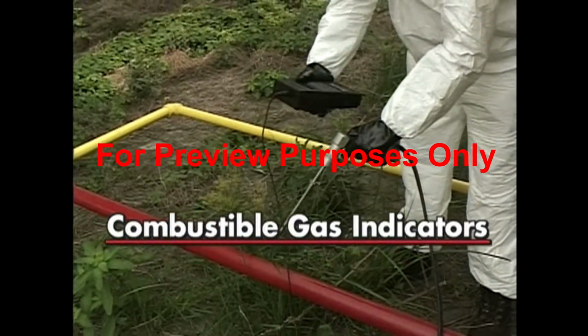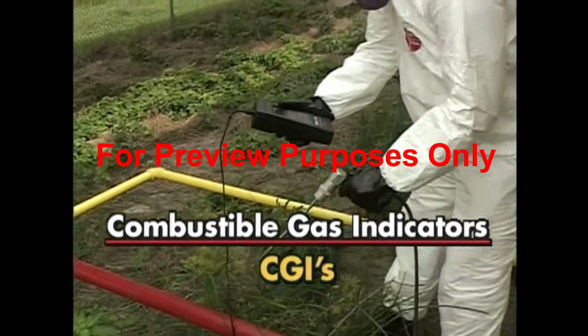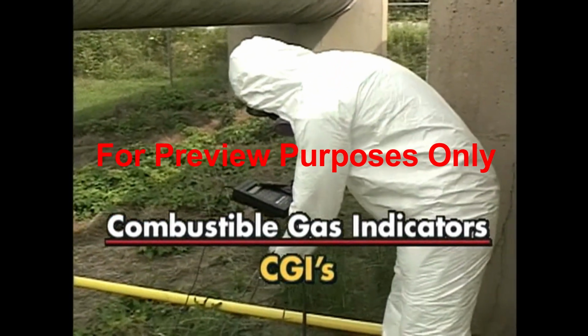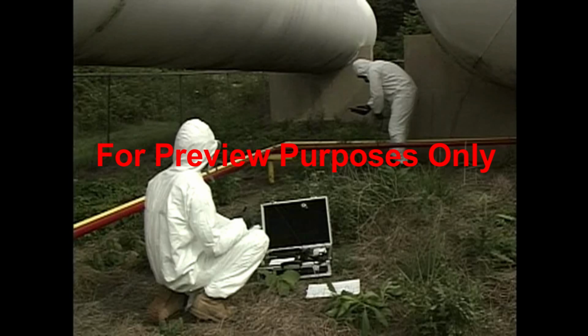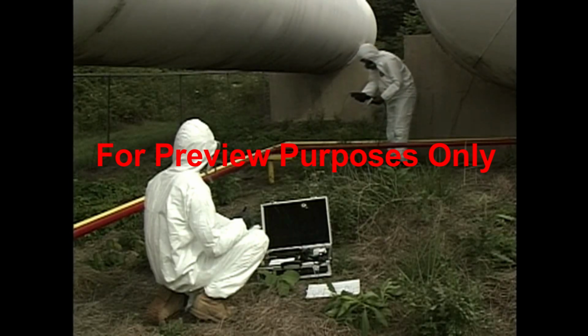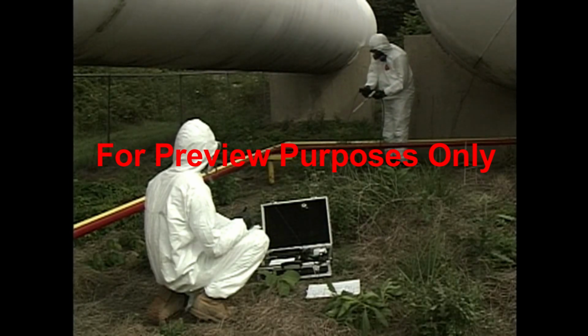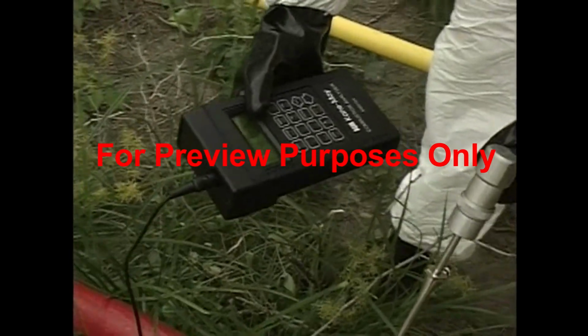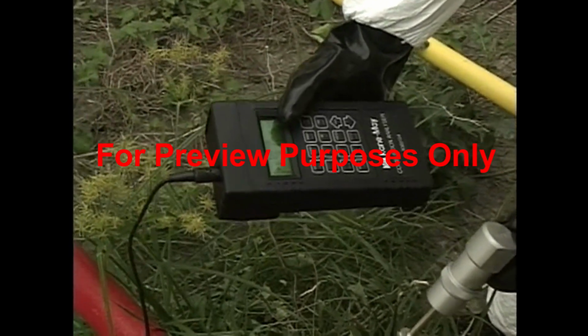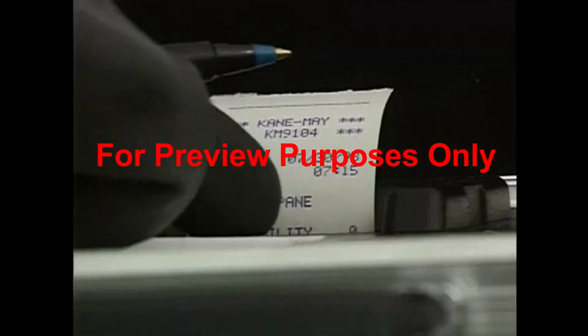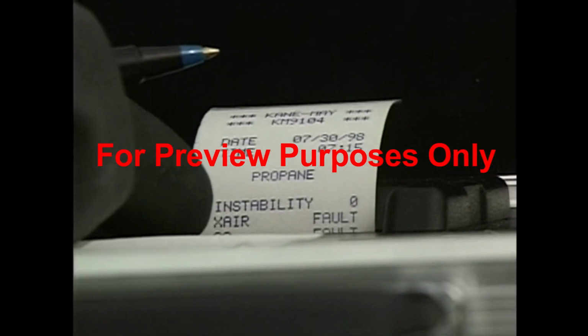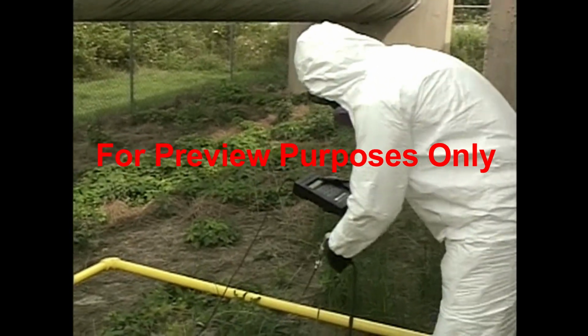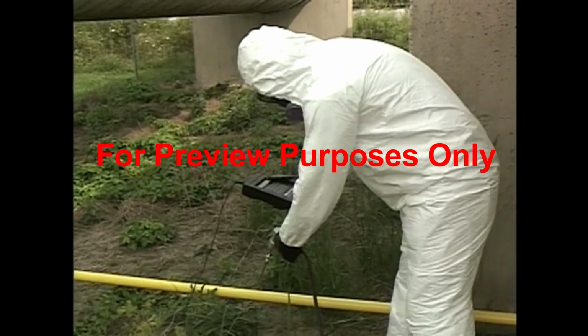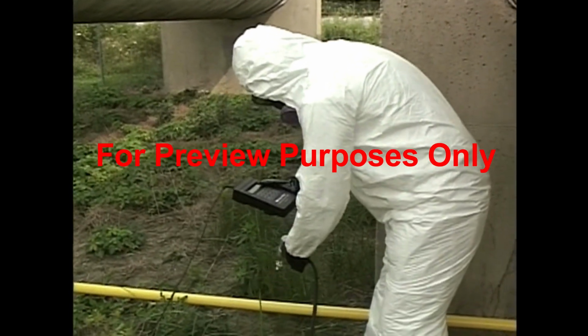Combustible gas indicators, also known as CGIs, detect gases which could ignite. A CGI burns a small quantity of gas by exposing it to a heated filament. The hotter that filament gets, the greater the concentration of the gas in the air. Because CGIs contain a potential ignition source, they should never be used in any area where the oxygen content is unknown.